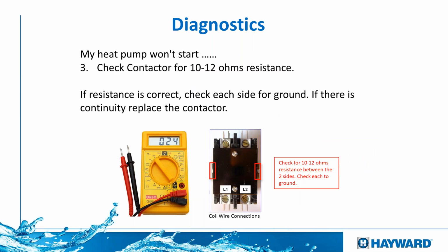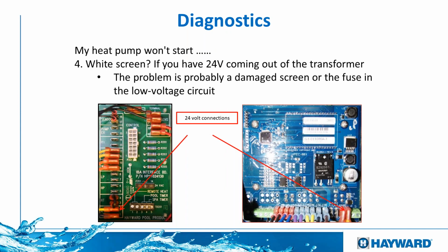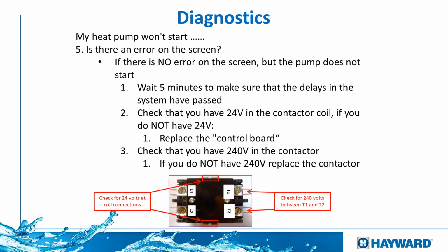If you do have 24 volts and the heat pump is calling for heat, then this is the contactor. And on the sides, that's where you have to check, just make sure that you have 24 volts coming in. If those 24 volts are coming in, that contactor should close and send the voltage to the compressor. Here you see the 24 volts, it comes from the transformer to the board, and then the two yellow wires are going to be the 24 volts that go to the coil of the contactor. So if we have 24 volts going to the contactor, 240 should go out of the contactor to the compressor and the fan.